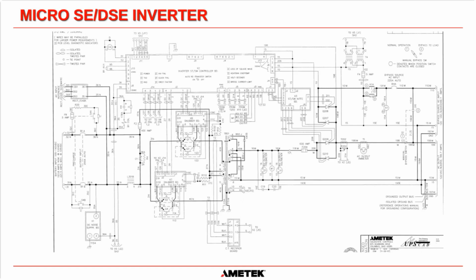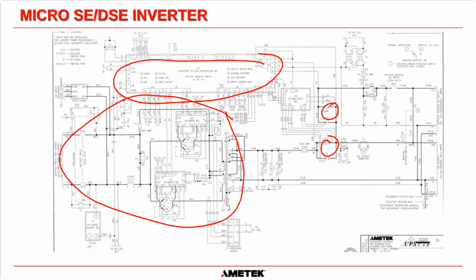Now, when you place it inside one of our drawings, it can look extremely complicated because there are so many other wires connected in there. There's a control board up here. We've got a static switch here. But here is our inverter bridge right here inside one of our DSE systems. And what you can see is this is our positive. So forget about the breaker and everything just now and the fuse. We are going here and we're going down here, and look, we are going to the center of that transformer. It's exactly the same as the drawing that I just showed you. And in this drawing, we have two IGBTs in parallel because we obviously needed more current in this system. And that's all we do.